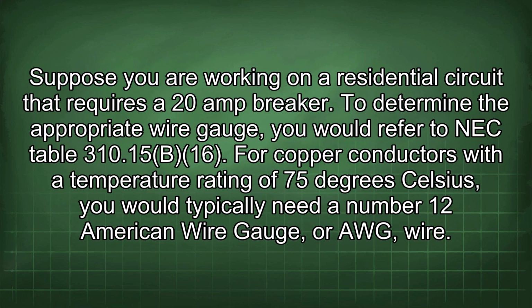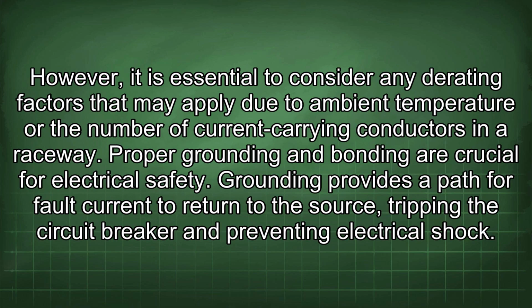temperature. Suppose you are working on a residential circuit that requires a 20 amp breaker. To determine the appropriate wire gauge, you would refer to NEC Table 310.15(B)(16). For copper conductors with a temperature rating of 75 degrees Celsius, you would typically need a number 12 American Wire Gauge, or AWG wire. However, it is essential to consider any derating factors that may apply due to ambient temperature or the number of current-carrying conductors in a raceway.